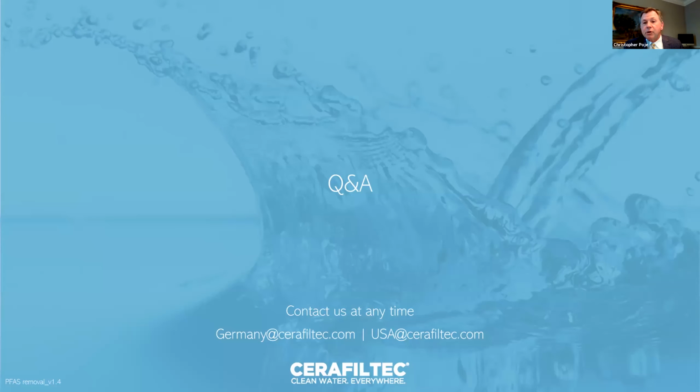Yeah, so as far as the ceramic lifetime goes, the standard warranty is 20 years, and there is nothing in the water or wastewater treatment, any range of pH or material that we might throw at them in a typical waste stream that's going to impact that. With regular backwash and occasional CIP clean, those membranes will function unabated for 20 years.